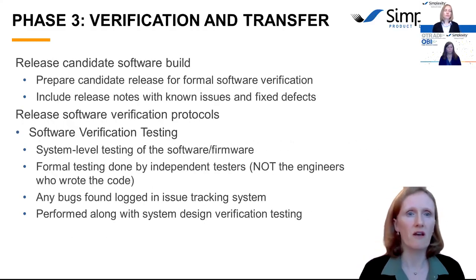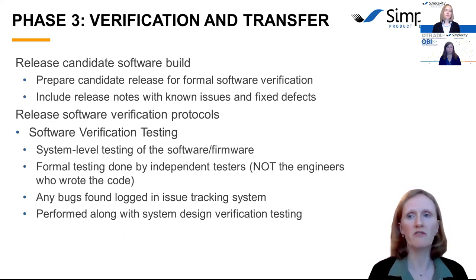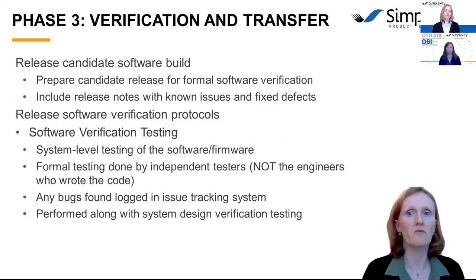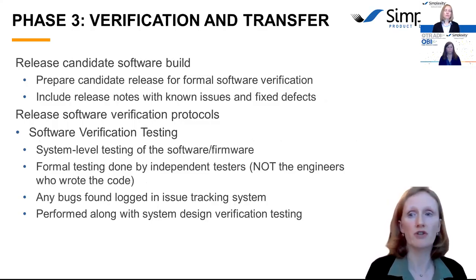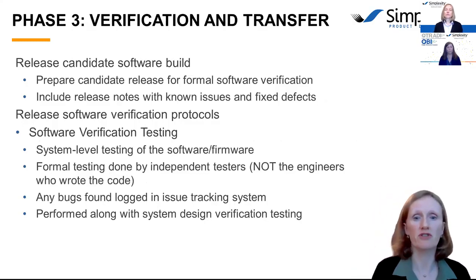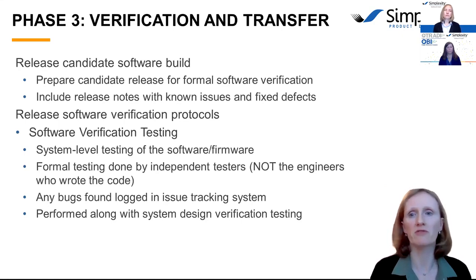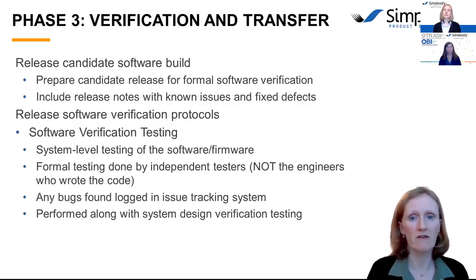In phase 3, the team's focus turns away from development and towards verification. The software system verification test protocols would have been released at the end of phase 2, typically written by the quality engineer with input from the software engineers, or possibly even more collaboratively. And the team will execute dry runs and fix final issues with the software or the protocols themselves. Hopefully, before you run formal software verification, you have pretty high confidence that your software is going to pass.